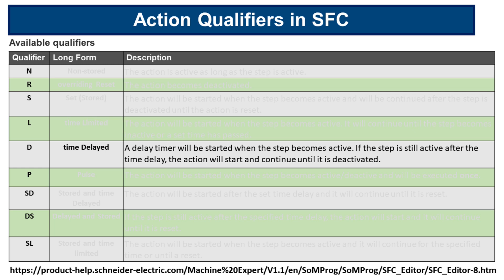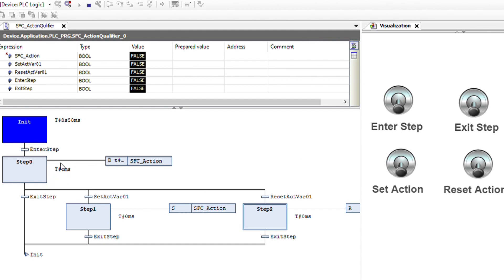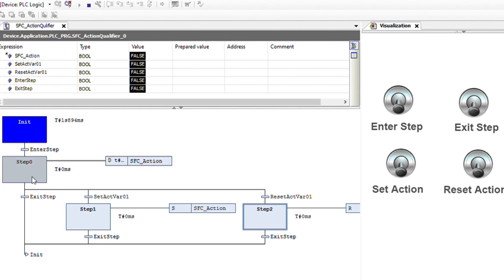The next qualifier is D, which stands for time delayed. A delay timer will be started when the step becomes active. If the step is still active after the time delay, the action will start and continue until it is deactivated. I changed the qualifier to D and kept the time as three seconds. After three seconds that step 0 is active, the action will become true. When we reach three seconds, action becomes true and remains true until we leave the step. If we enter into the step and then leave before the delay is over, the action will remain false. That's the way the D qualifier works.